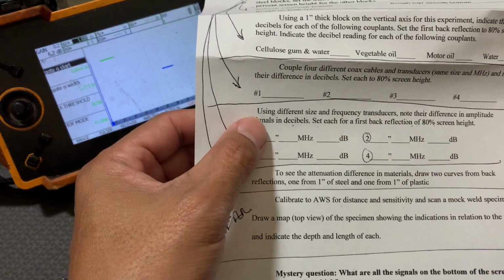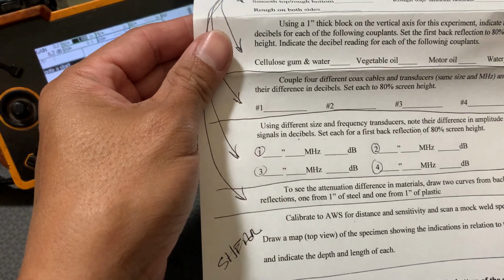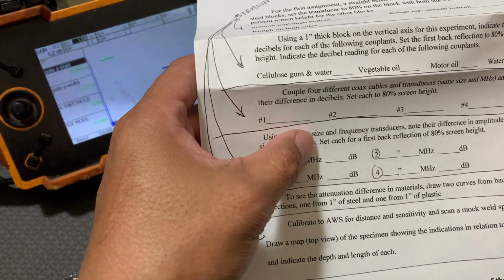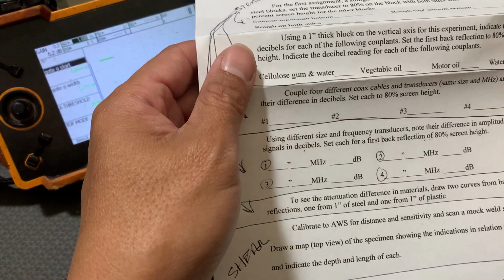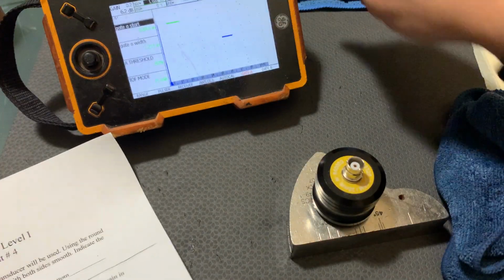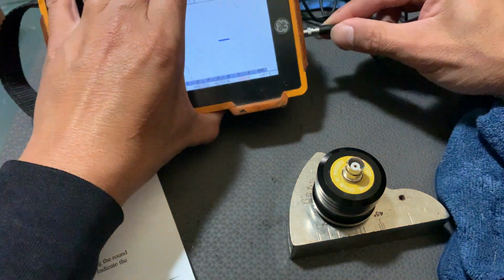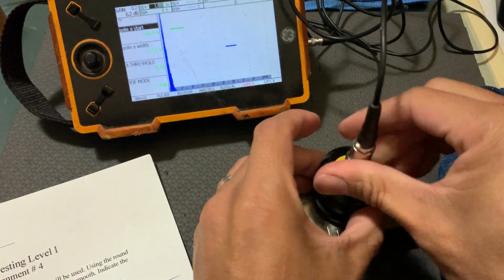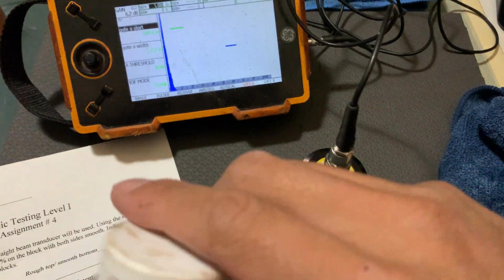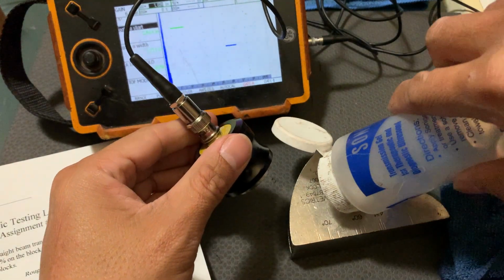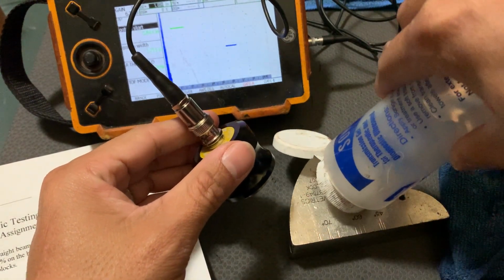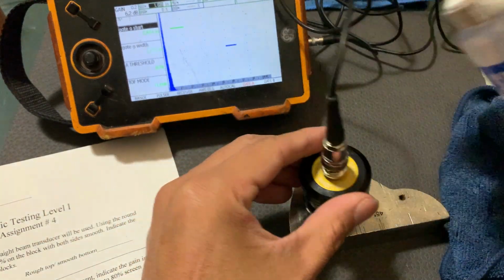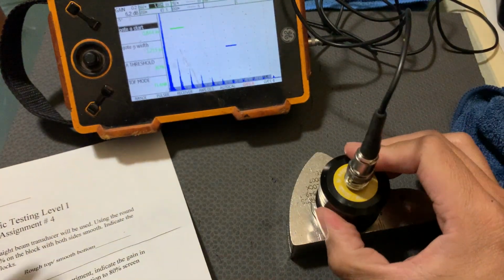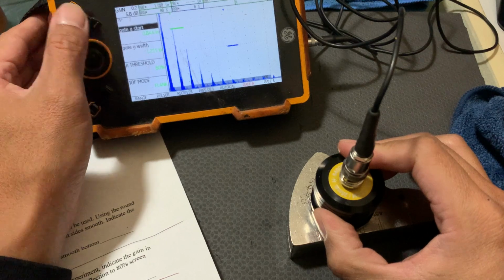Next assignment, using different size frequency transducers and note their difference in amplitude, signals, and decibels. Set each for the first back reflection at 80% screen height. So what you do on this one, use what you got on your machine. Set it to 80% screen height.